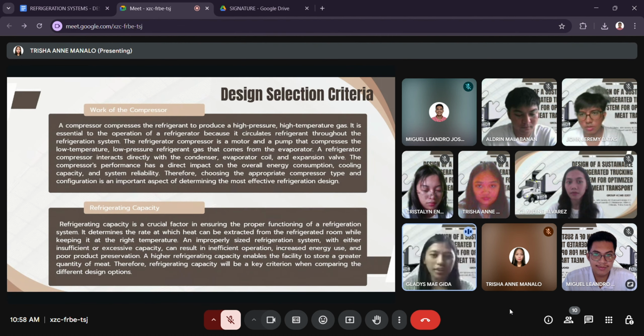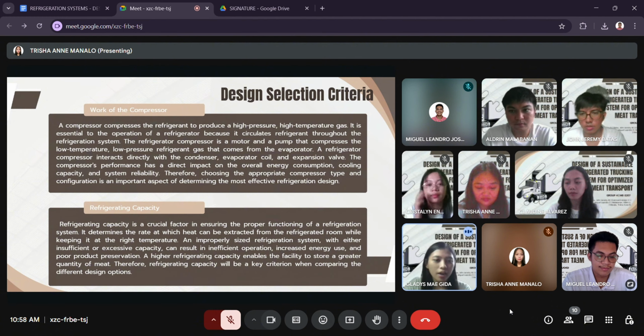For the design selection criteria, first we have the work of the compressor. A compressor compresses the refrigerant to produce a high pressure, high temperature gas. It is essential to the operation of a refrigerator because it circulates refrigerant throughout the refrigeration system. The refrigerator compressor is a motor and a pump that compresses the low temperature, low pressure refrigerant gas that comes from the evaporator. A refrigerator compressor interacts directly with the condenser, evaporator coil, and expansion valve. The compressor's performance has a direct impact on the overall energy consumption, cooling capacity, and system reliability. Therefore, choosing the appropriate compressor type and configuration is an important aspect of determining the most effective refrigeration design.